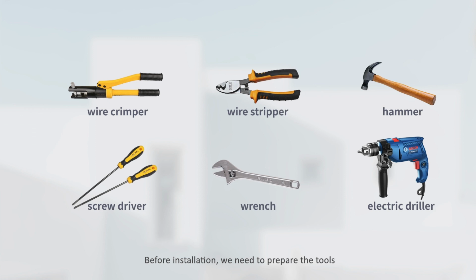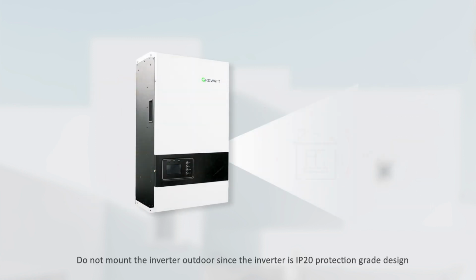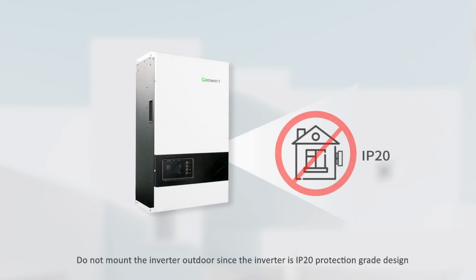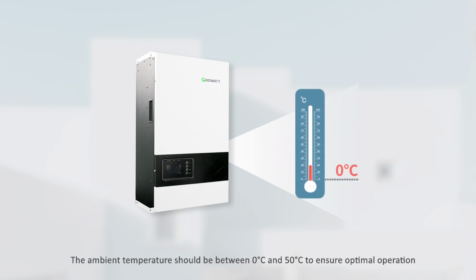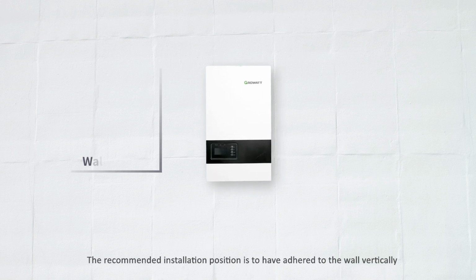Before installation, we need to prepare the tools. Do not mount the inverter outdoors since the inverter is an IP20 protection grade design. The ambient temperature should be between 0 and 50 degrees Celsius to ensure optimal operation. The recommended installation position is to have it adhered to the wall vertically.